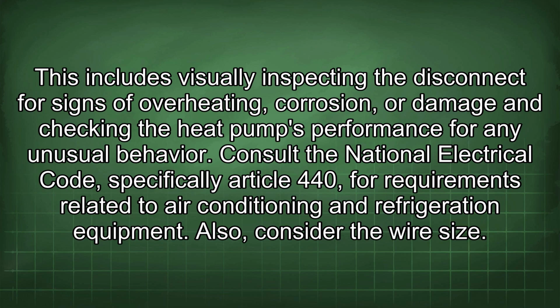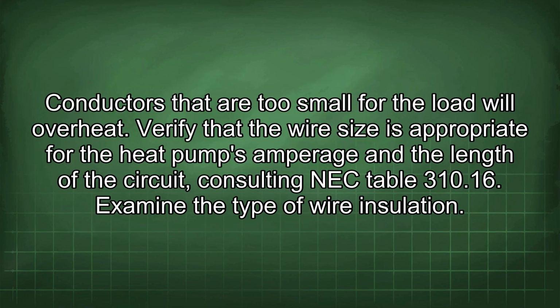Also, consider the wire size. Conductors that are too small for the load will overheat. Verify that the wire size is appropriate for the heat pump's amperage and the length of the circuit, consulting NEC Table 310.16. Examine the type of wire insulation.